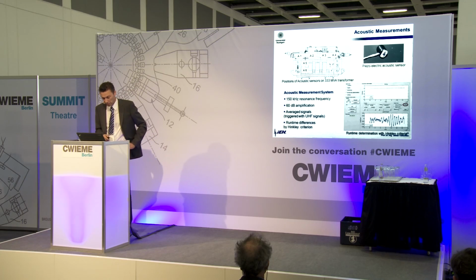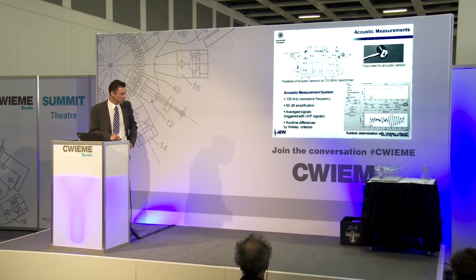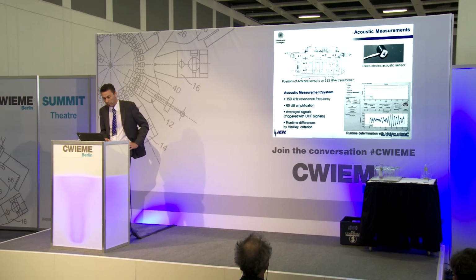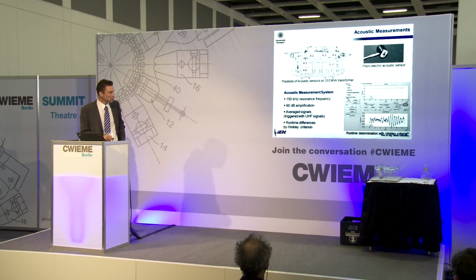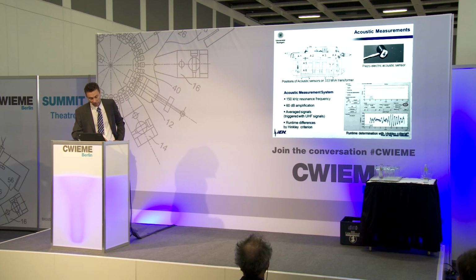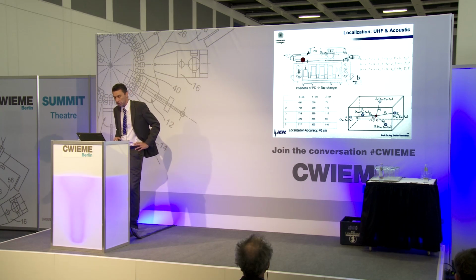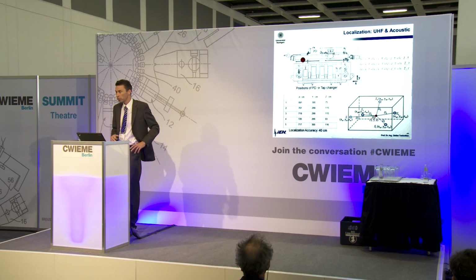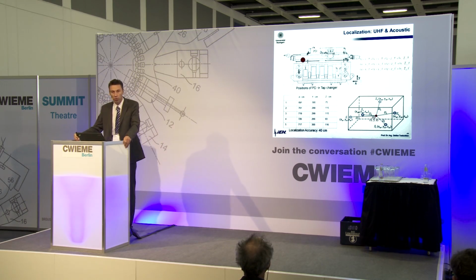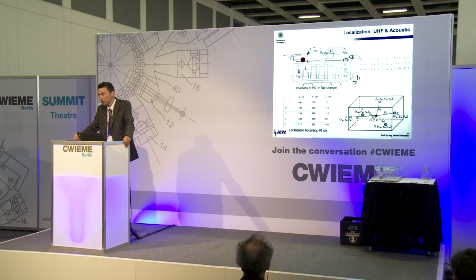To determine this arrival time, we are using a so-called Hinkley criterion, which is based on the energy content. I don't know if you can see here this green curve. It has its minimum here, and this means that exactly at this time is the arrival time. So we had the arrival times of several microphones, and so we could localize the PD, let's say, near the tap changer. And you know, the tap changer is accessible if you open the transformer, so it was decided to bring this transformer back to the factory.